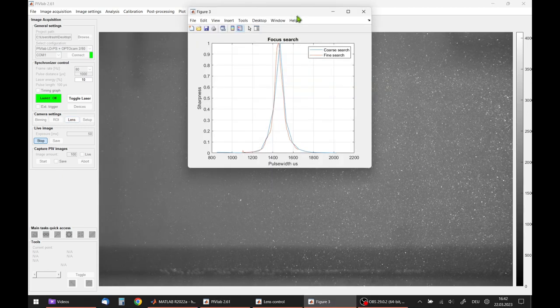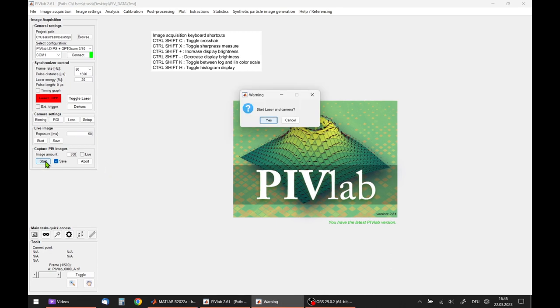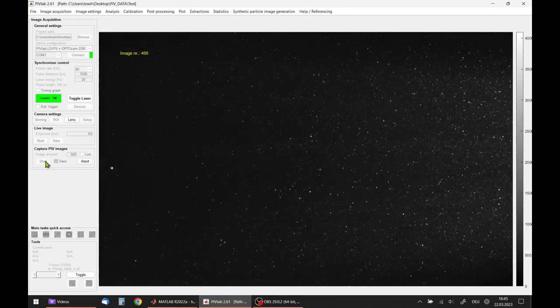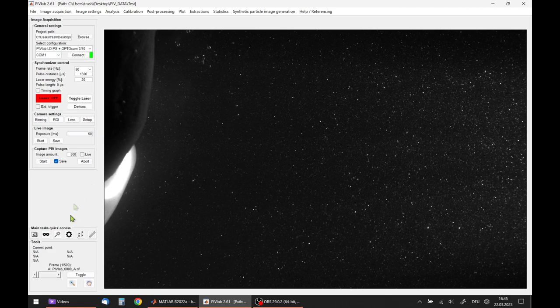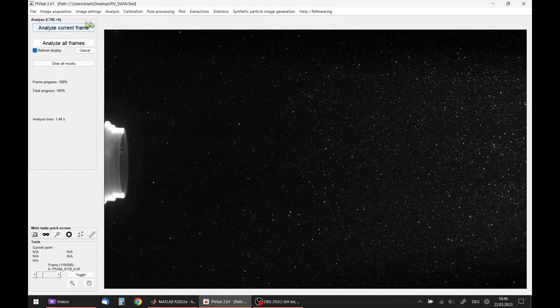Then select the suitable configuration — in this case the 5W laser and the OptoCam, which is detected automatically. I am changing the camera bit depth to 12 bits, setting the frame rate to 80 Hz, then toggling on the laser and starting the live image preview, which runs unsynchronized at this point. I select the correct lens and hit autofocus. The autofocus then starts to focus on the particle pattern illuminated by the laser. After that, switch off the laser and camera, and select the pulse distance or interframe time — I found 1500 microseconds to be a good choice for this experiment. We want to save 500 double images.